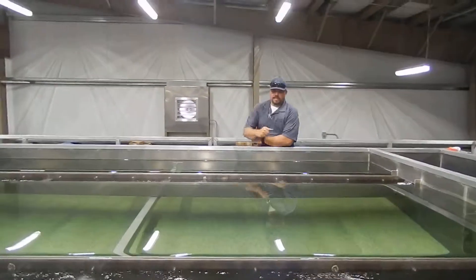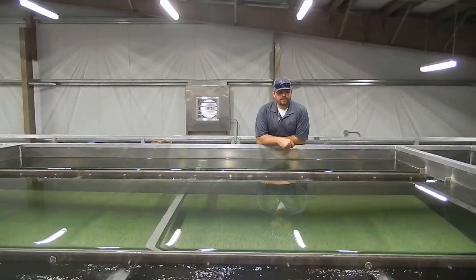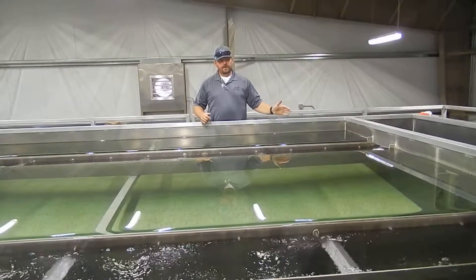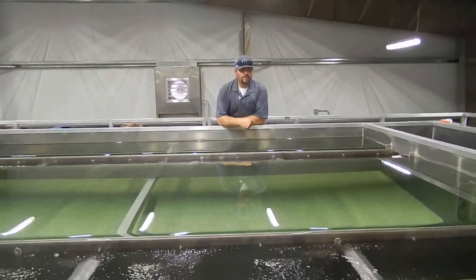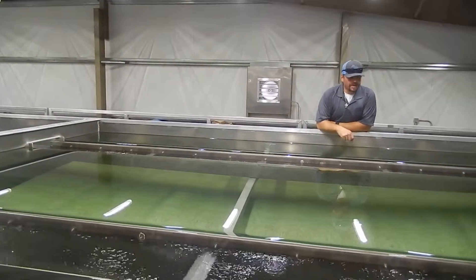So what we're looking at here is the first portion of our up-flow clarifier. As we saw in the graphic earlier, the water is actually coming up through the underdrain here. And there are 42 inches of this gravel. This is monomedia — the same media all the way to the underdrain.